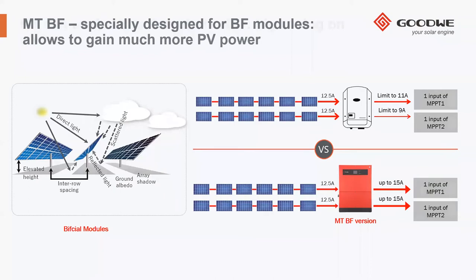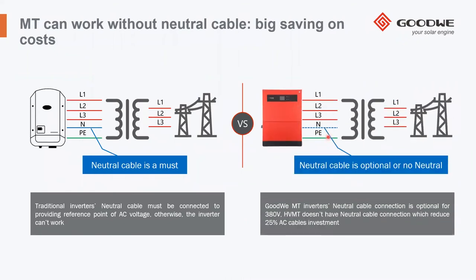Another feature which is quite important is the possibility for our inverter to work without the neutral cable. So it's optional. It's clear that if you consider a large installation, the fact that you can save on the cost of one cable could be a relevant saving. So you have this possibility here as standard. So you can use or you cannot use the neutral cable, it is not a problem. And so this is, as I said, another big saving for you.